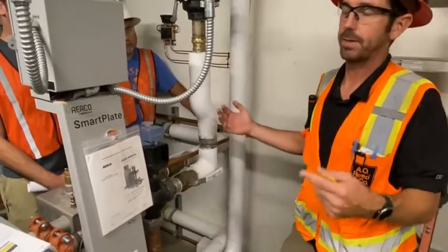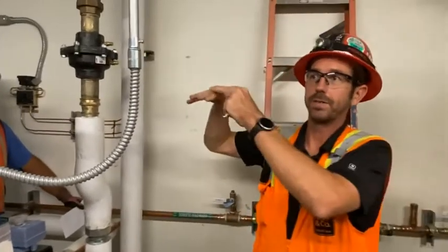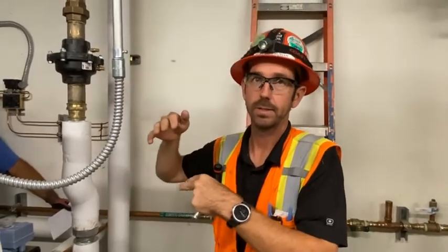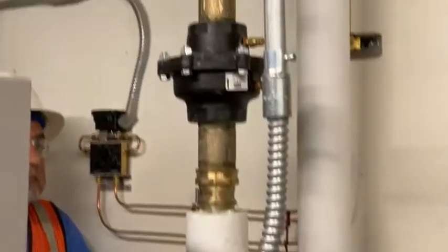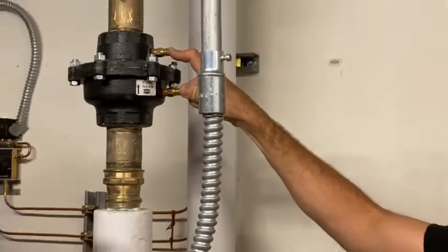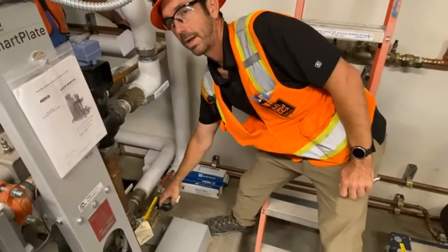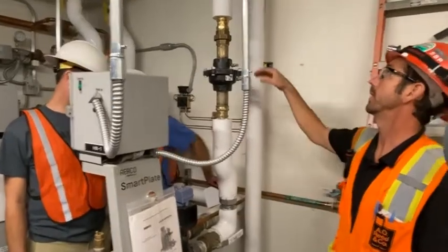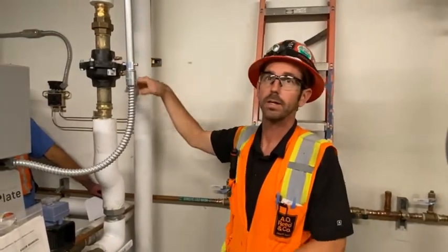If we can't keep up with the tanks, this is an auto-flow valve — there's a calculated orifice with a spring that always gives you 75 GPM within a certain differential pressure range. You'd have to look up the manual to find the specific range, something like 2 to 35 PSI differential. If you have that differential, you get 75 GPM. If not, check if the strainer is clean. If the strainer's clear, shut the unit down, break the union, unthread the device, and see if something got stuck.